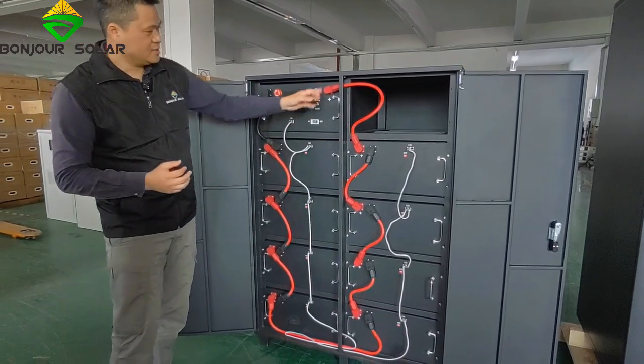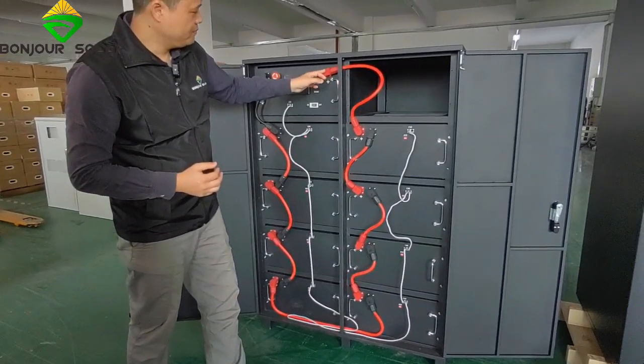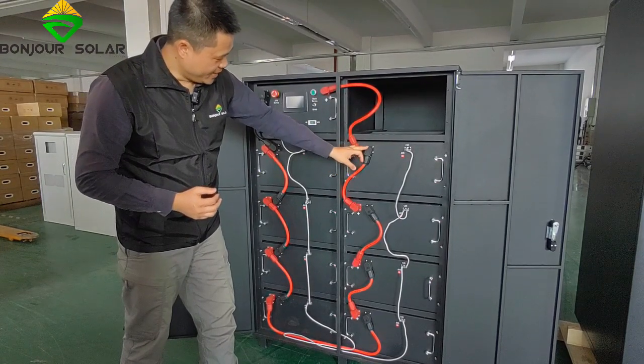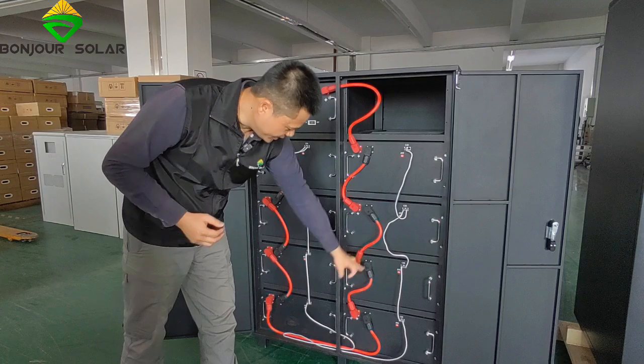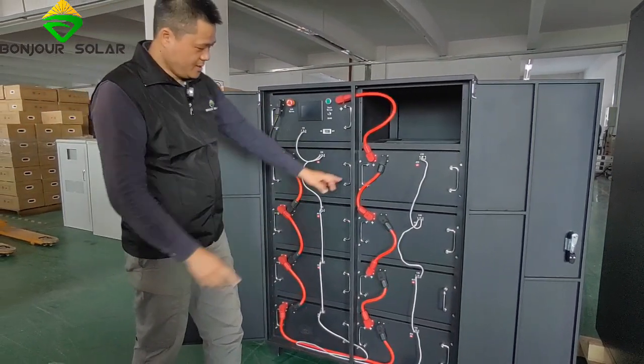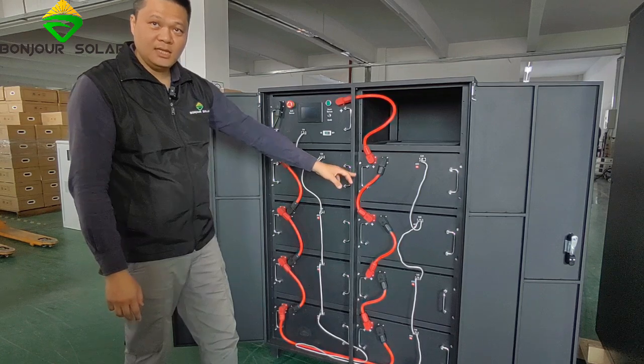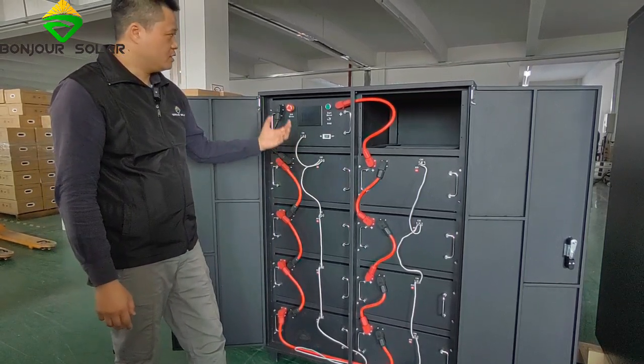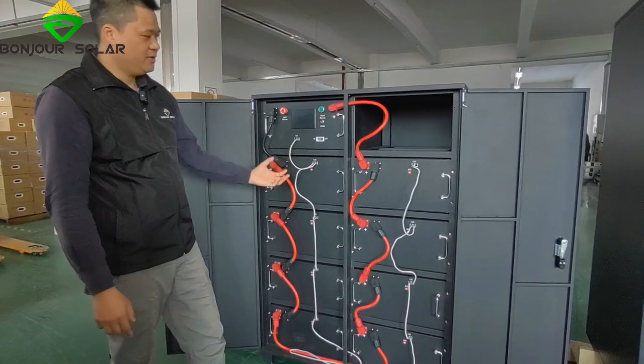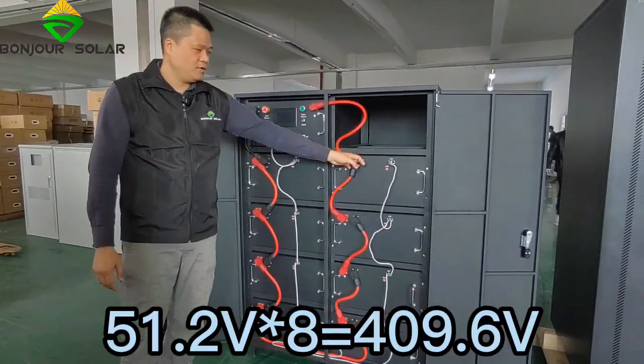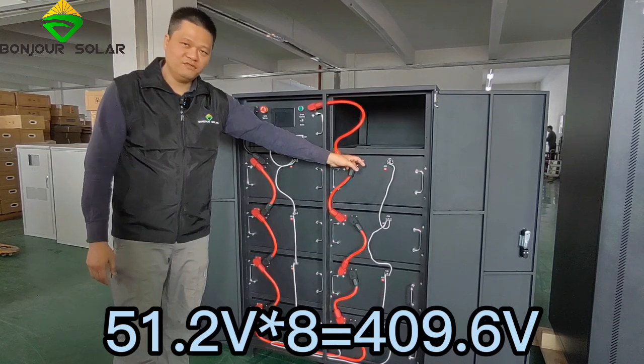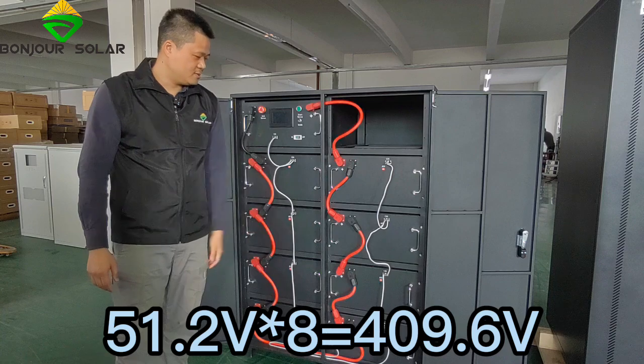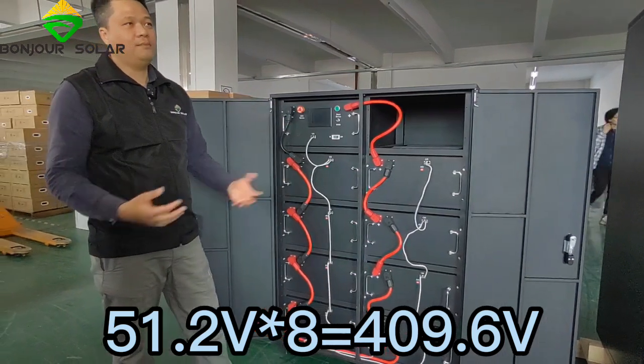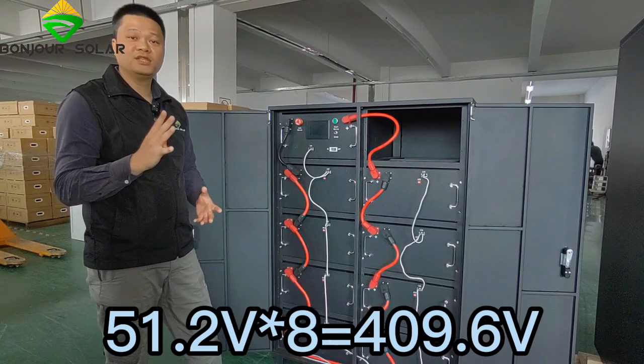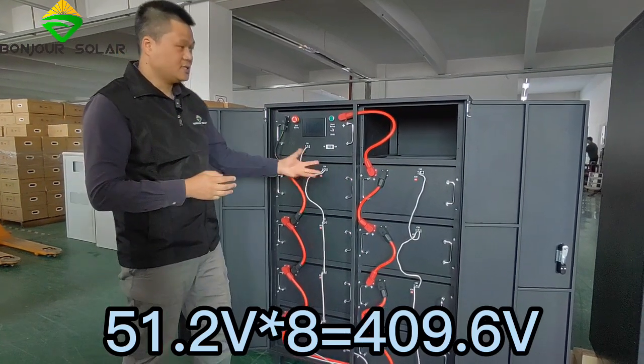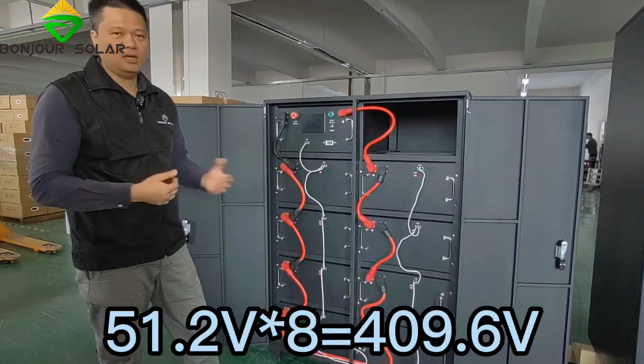We can see clearly positive, negative, positive, negative - the 8 modules are connected in series. In series connection they give a total high voltage. Each module is 51.2 volts, times 8 pieces, so we get about 400 volts total for the high voltage system, connected directly to the inverter.